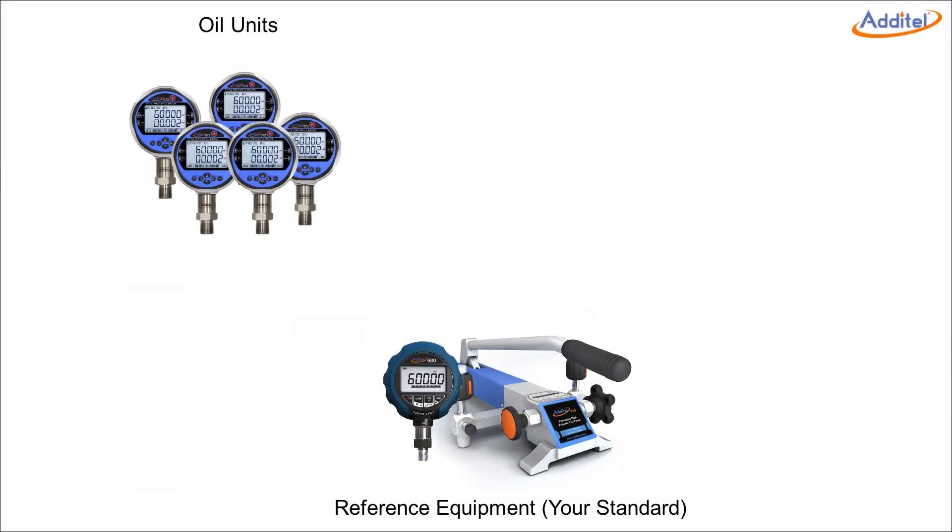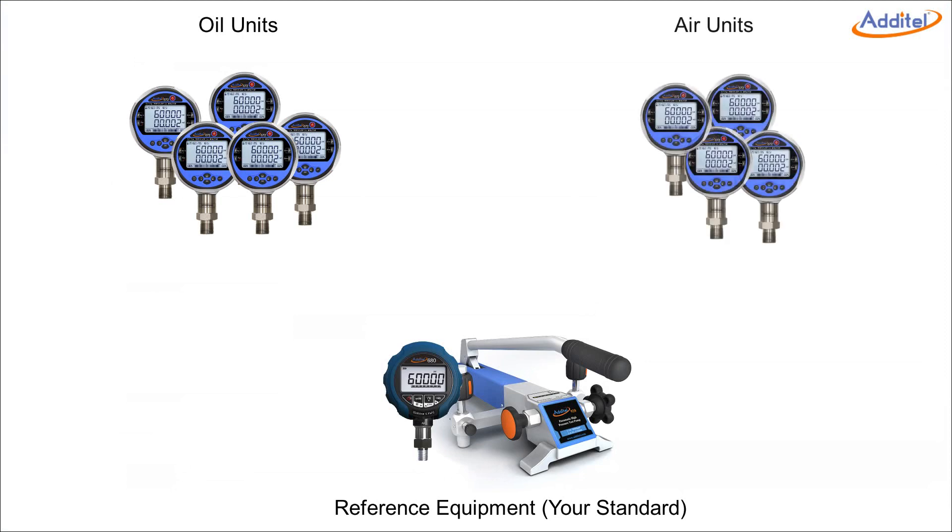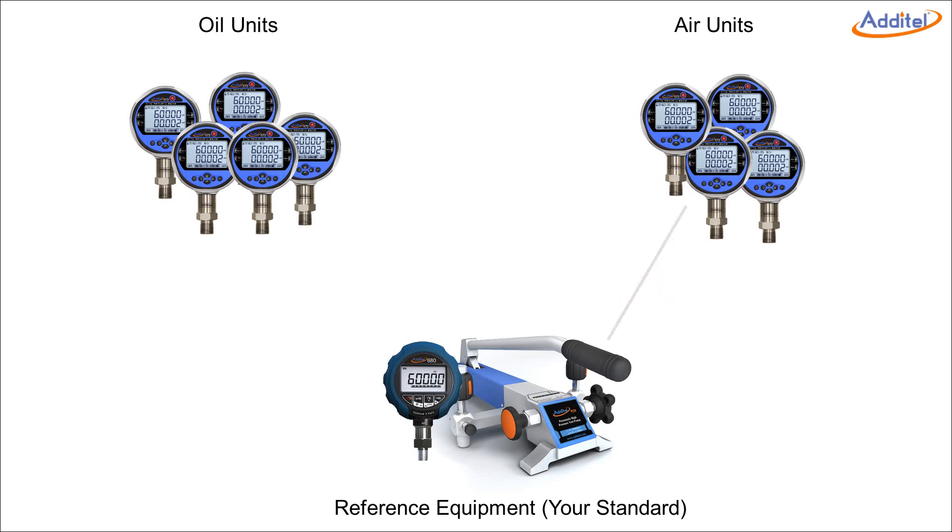Let's say that you have some units you calibrate that use oil as a medium, and some units that use air as a medium. Most of the time, you're not going to use the same reference to calibrate both the oil and the air system, as it could cause serious contamination problems.